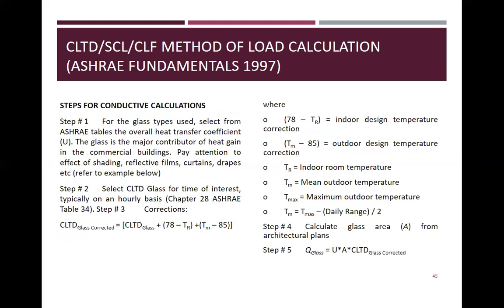Now, steps for conductive calculation. Step number 1. For the glass type used, select from the table the overall heat transfer coefficient U. The glass is the major contributor of heat gain in commercial buildings. Pay attention to the effect of shading, reflective films, curtains, drapes, etc. Refer to the example below. Later.